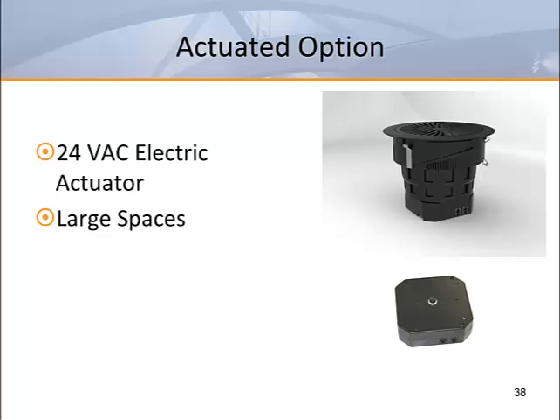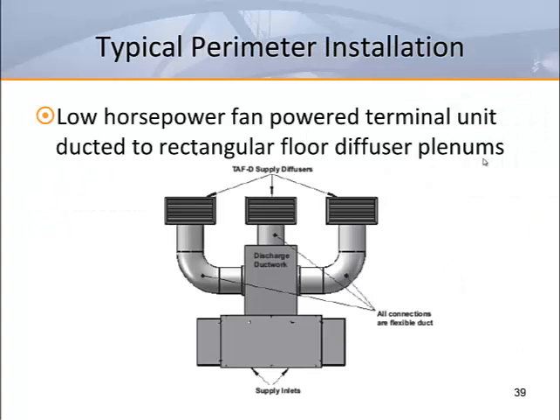The round swirl diffusers can be used with an actuator that is controlled by a zone thermostat. These installations are typical for common areas such as break rooms, lobbies, or large areas controlled by a single zone thermostat. For perimeter applications, while the loads in the core area remain fairly constant, loads on the perimeter change dynamically throughout the day depending on outdoor conditions. A common way of handling perimeter load is the use of fan-powered terminal units, which are ducted to rectangular diffusers that are rated at higher airflows than interior swirl diffusers.